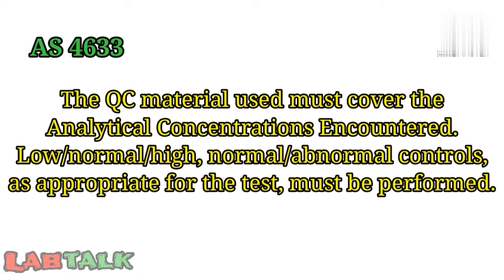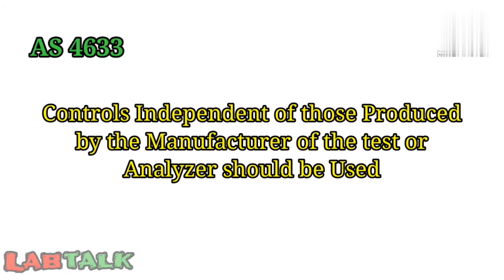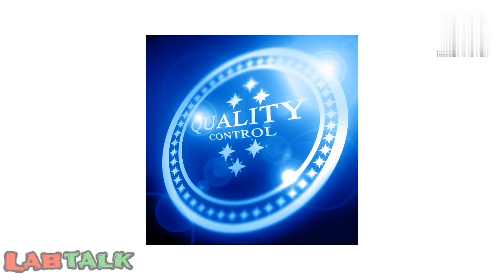Regarding control materials, one recommendation comes from the Australian document AS 4633, a supplementary document for ISO 15189. It recommends that QC material must cover the analytical concentrations encountered and should include low, normal, high, and abnormal controls as appropriate for the test. A second recommendation is that controls independent of those produced by the manufacturer of the test or analyzer should be used — these are called third-party QC materials.